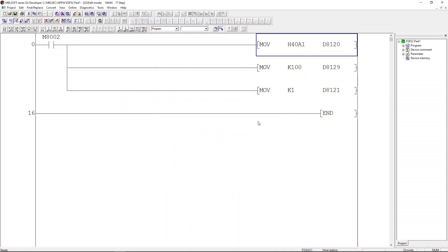The ladder is downloaded to the PLC. Next you will need to power cycle the PLC. Remember, M8002 will only toggle on after the PLC powers up. If you don't power cycle the PLC, the RS-485 setup code won't be executed.